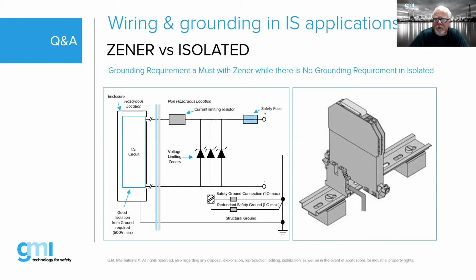The key thing to remember is that if you're mounting Zener barriers inside a cabinet, and that cabinet is a metallic cabinet, we want to make sure that the DIN rail is isolated. We don't want to interfere with the normal system ground in that scenario. So that's really the key thing to remember. If we are using Zener barriers and using that DIN rail for grounding, we want to make sure that the DIN rail is isolated in some way, shape, or form from the enclosure itself.